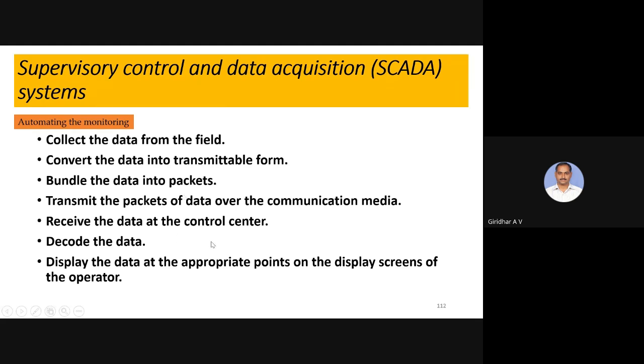There we are using different communication protocol standards. Suppose there is very critical data for protection, where appropriate control should be done. A particular communication that works at a very fast rate can be used for that. Some data you may not require at a very fast rate, and that data can be sent over other communication. In that way, cost aspects and everything can be optimized.